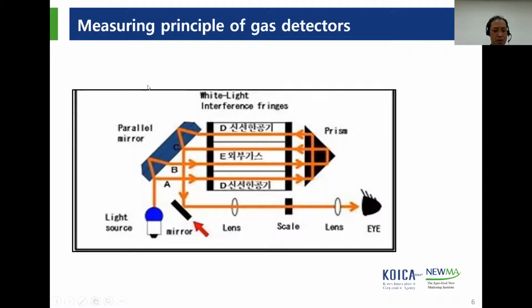The measuring principle of the gas detectors made by Riken Keiki is to compare the refractive index of fumigation gas, such as methyl bromide, by setting the refractive index of air to 0.